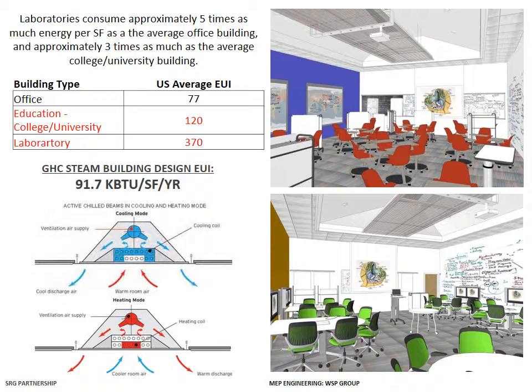Labs are provided with VAV rooftop air handling units for heating, cooling, and exhaust. Office spaces use radiant floor heat and eliminate refrigerant-based cooling. Cooling is accomplished using natural ventilation with operable windows, ceiling fans, plus mass activation of the radiant floor with cool water. Classrooms are provided with chilled beams to provide heating and cooling.